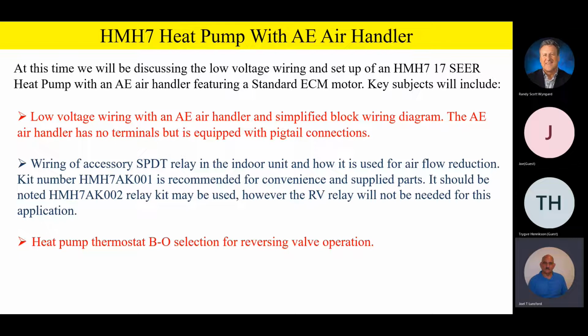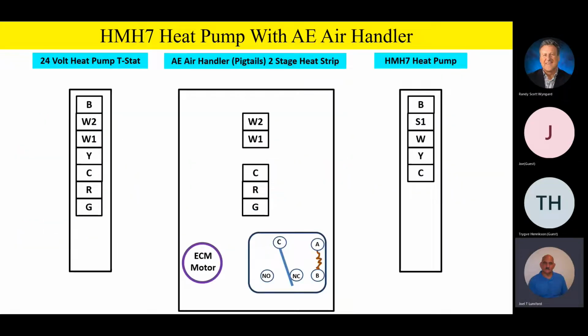The 002 kit you have to use on the variable speed products, but it's universal in the fact that if you do want to use it on an AE air handler, in our example, you will not use the RV relay. You'll just be using one of the relays on that 002 kit if needed. It should be noted also that a heat pump thermostat has to be used with the HMH7, and that thermostat has to have a BO selection for reversing valve operation. We'll get a little more into that when we start our low voltage wiring review. So again, the heat pump thermostat has to have the BO selection for reversing valve operation. Okay, let's talk a little bit about a standard 24-volt heat pump thermostat with the AE air handler.